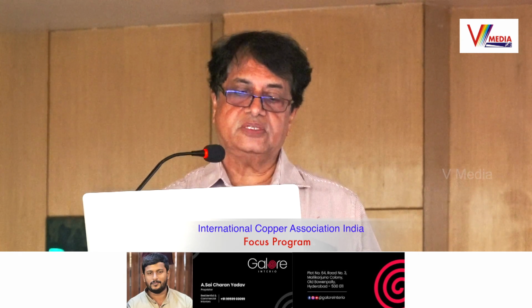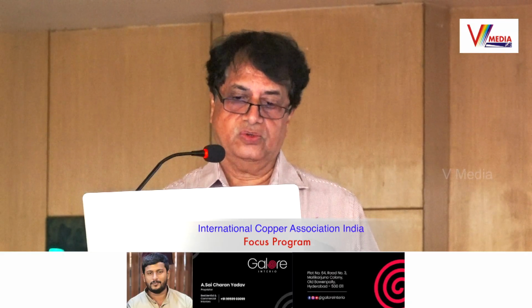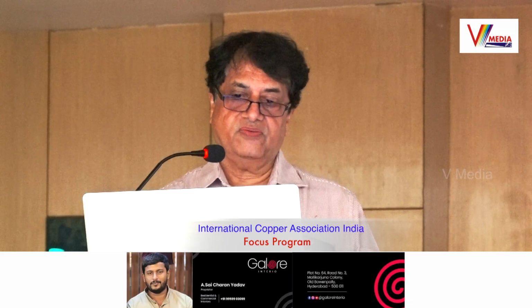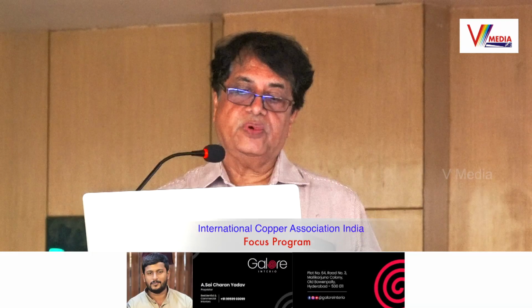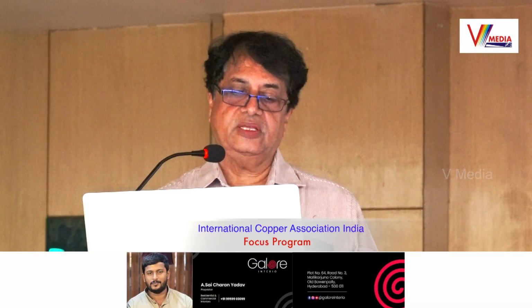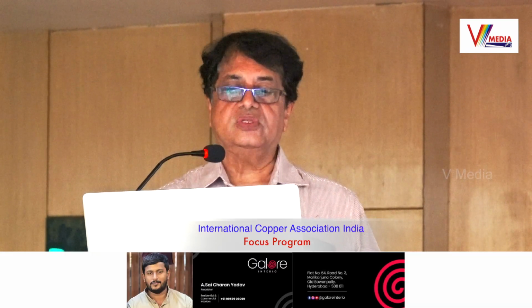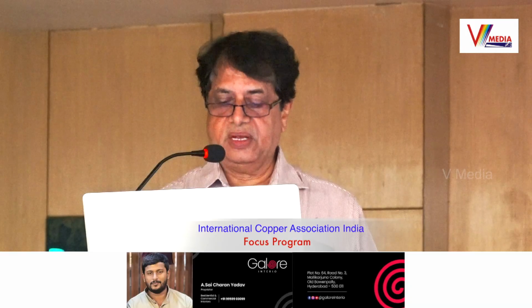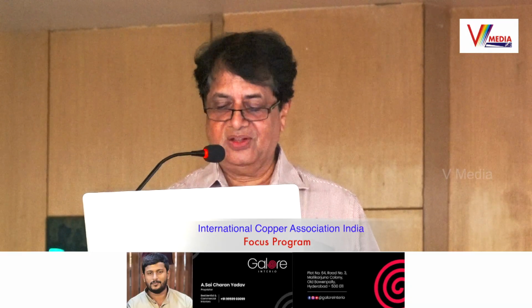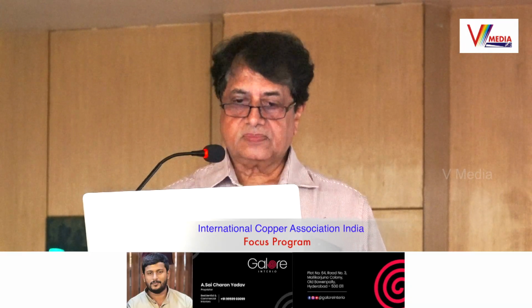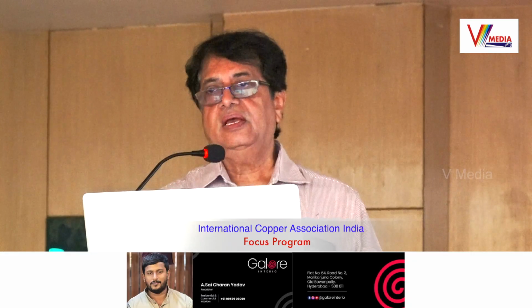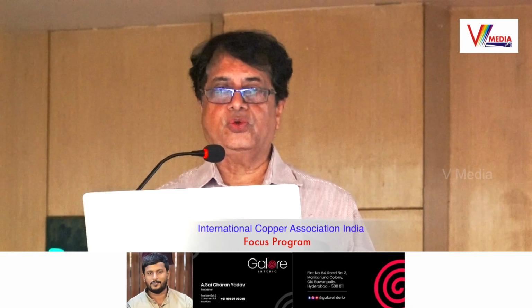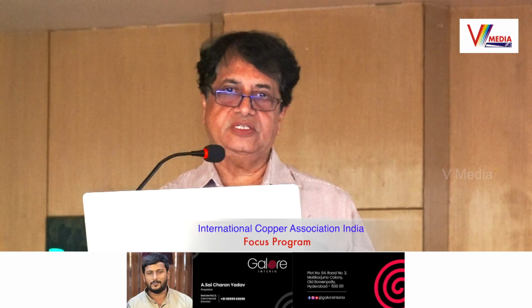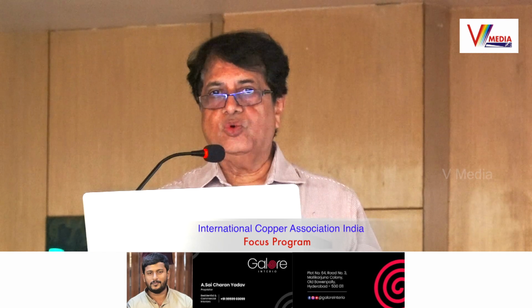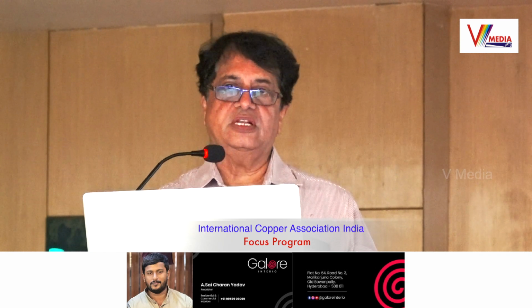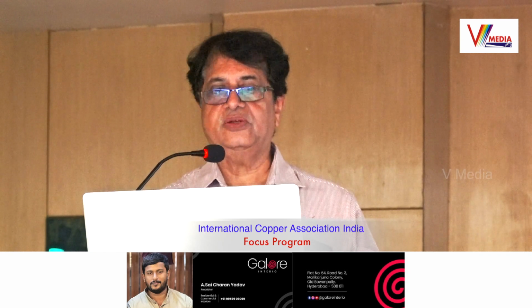These are the actual pictures shown in the adjacent frames, where the electrical transformers have been installed on the upper floor. And of course these transformers are dry type, not oil type transformers. Why oil type transformers are not there, we will see in our next slide. Transformers are required to be cooled, and the cooling medium is different. The most efficient way to cool the transformer is a liquid. That liquid comes in two classes.